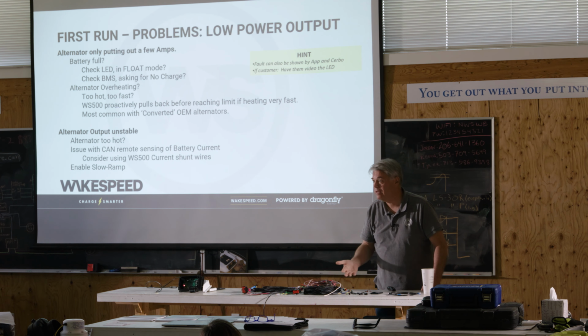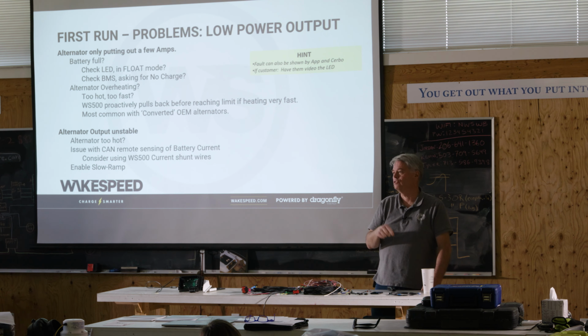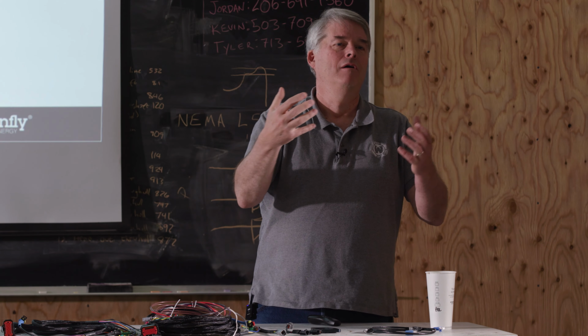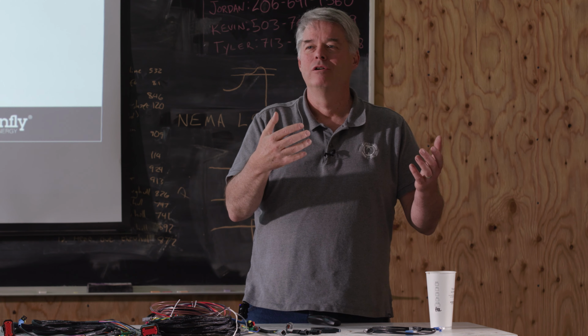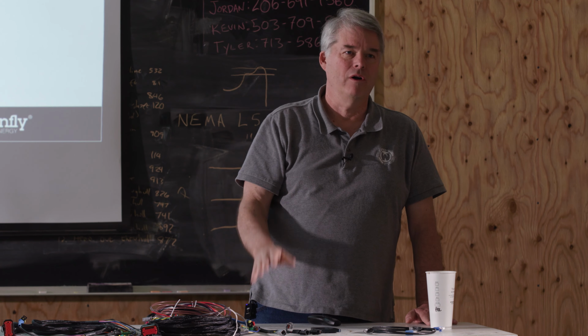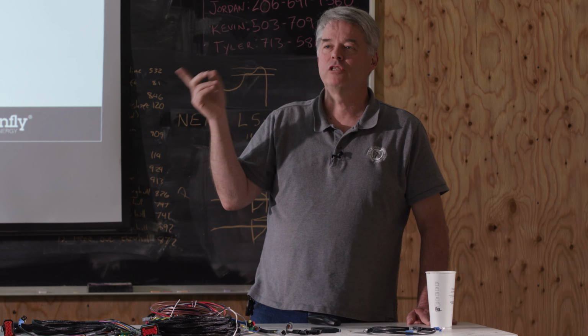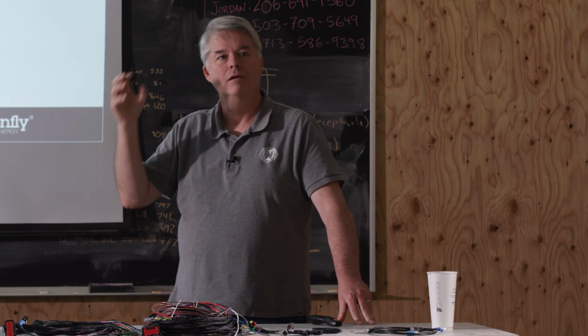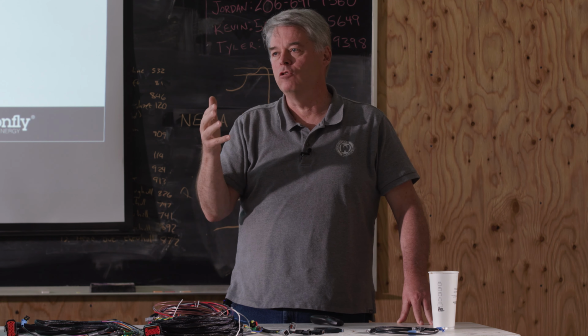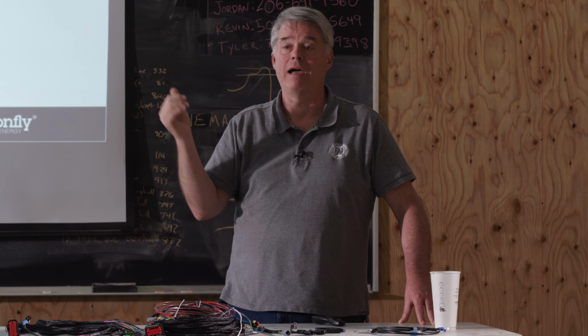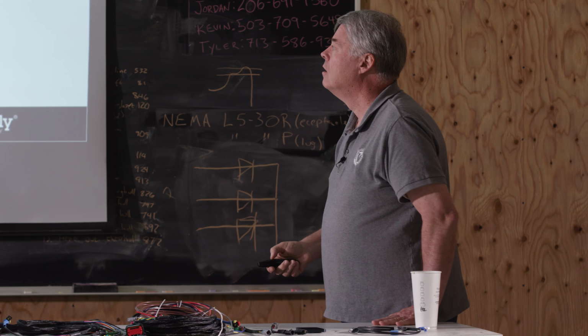The solution is to derate those percentages, whether it's the normal percentage or the half power, that 100% or 90%, cut that back to a smaller number. Because what it's saying is that alternator is not capable in that install of being driven that hard. So give the Wakespeed a little bit of help: when we're under temperature, don't let us put the gas all the way to the floor, let us just manage the gas a bit. So if you see that kind of temperature cycling, improve your cooling on your alternator and/or reduce the derate factors to solve it.